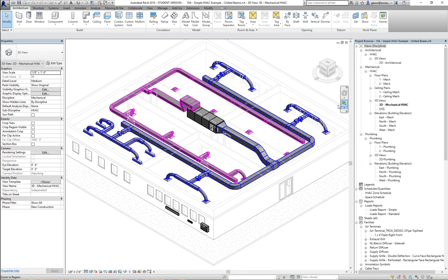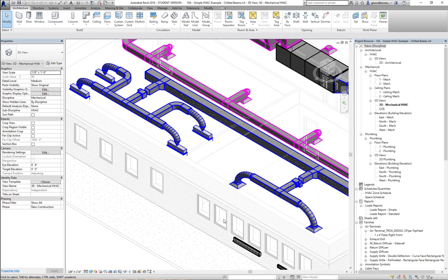we illustrate just two different systems. In the lower right, the supply air is coming in, going to the VAV, and then going directly to these air terminals. In the upper left, the central air is coming in and going to the VAV. In this scenario, the VAV would just be controlling the amount of volume, not actually heating and cooling, because these units out here at the end are chilled beams, and they're doing the heating and cooling right at the end point for the room.